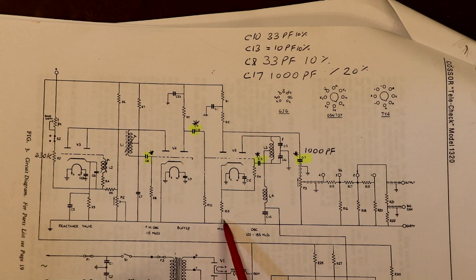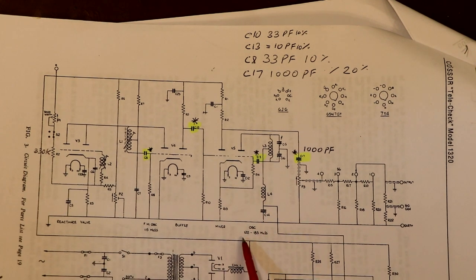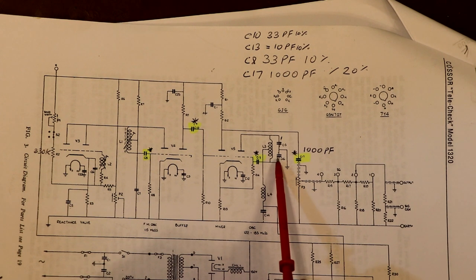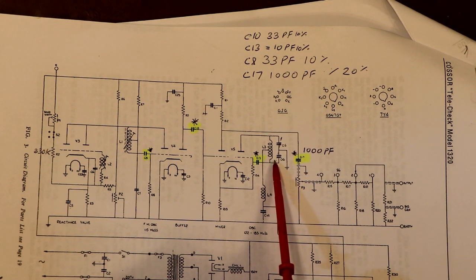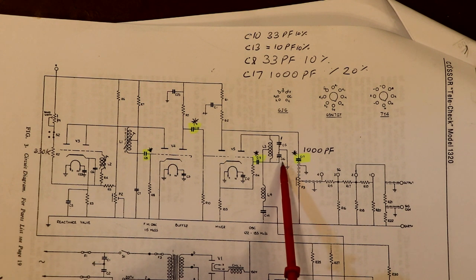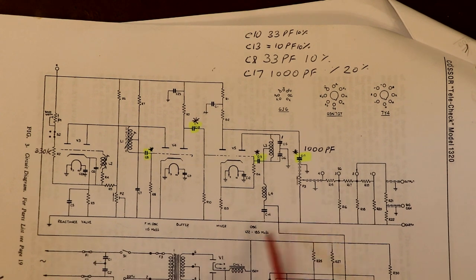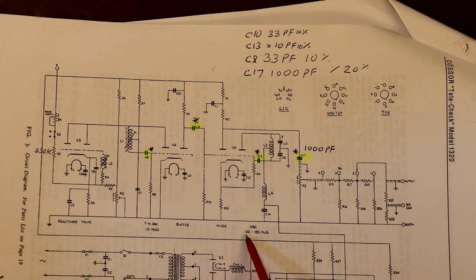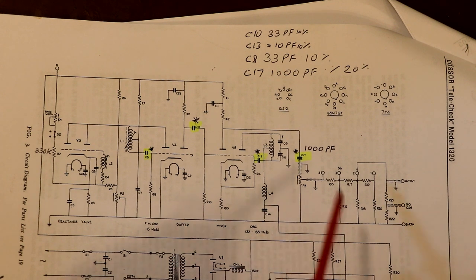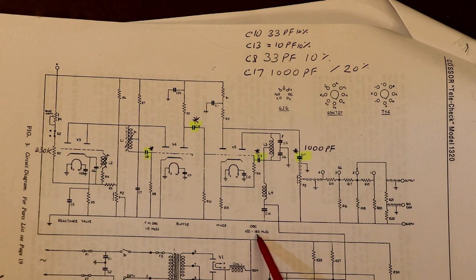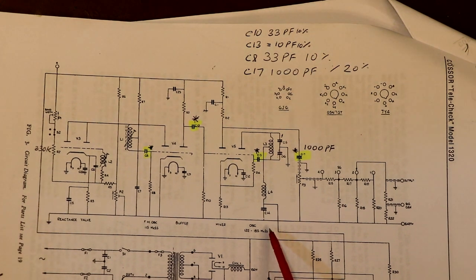According to our circuit diagram, we've got an oscillator that's between 122 and 185 megahertz, with a variable capacitor that's the frequency control I was adjusting on the front of the instrument. But the markings on the front of the instrument say 7 to 70 megahertz, and yet this oscillator only goes between 122 and 185, and on the oscilloscope we were getting an output between 122 and 185 megahertz.